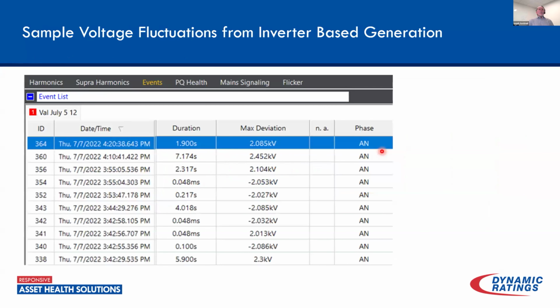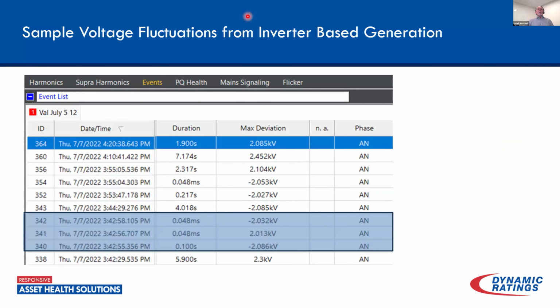In addition to that, we sort of talked about it before, but there can be a lot of voltage fluctuations when it comes to inverter-based generation. Again, the inverter-based system is basically a reactionary system. It's not relying on momentum, it's relying on just reacting to what it's seeing on the system and trying to compensate for that. If there's an event on the system, a fault on the system or something like that, that inverter is going to react and basically start pumping VARs onto the system.